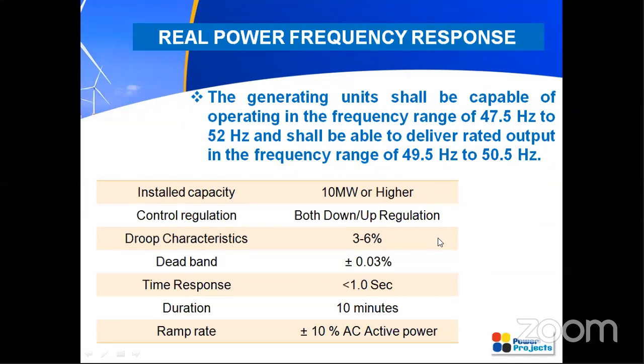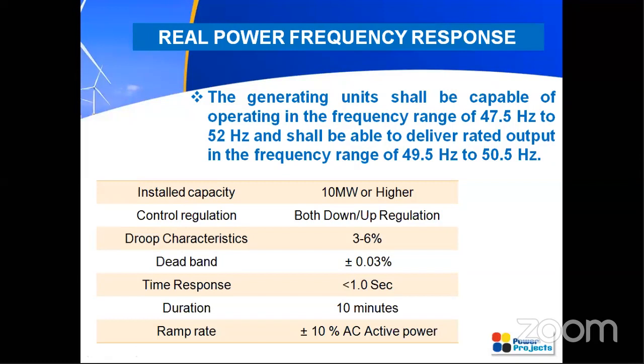So this has to be satisfied, and this is given in the grid code requirement. For any wind turbines of capacity 10 megawatt or higher, and operating with the voltage level of 33 kilovolt and higher, the generating unit should be equipped with the facility to control its active power injection to the grid. That is, it should control its active power injection at a set point as described by its load dispatch center, either the regional dispatch center or the state load dispatch center. So it has to control its frequency, that is, it has to control its active power injection.